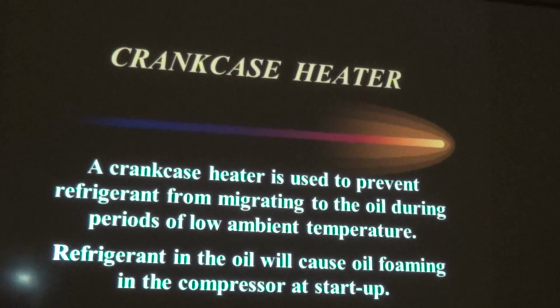A crankcase heater is often found in a larger split air conditioner and heat pump. A crankcase heater is used to prevent refrigerant from traveling to the oil in the compressor sump when the unit is turned off, during periods of low ambient temperature, or when the unit is not running. If you have excessive refrigerant in the oil, when the compressor does start up, it causes compressor foaming, which reduces the ability of the oil to lubricate, which is going to scramble your compressor.